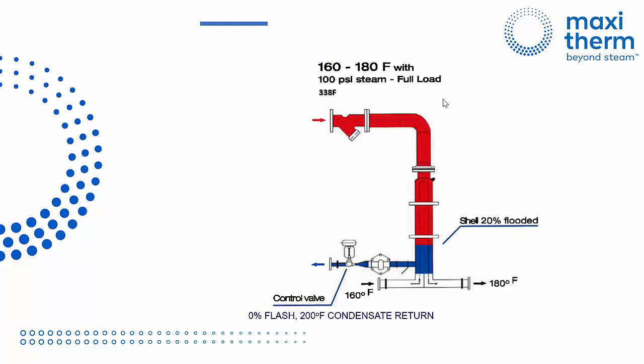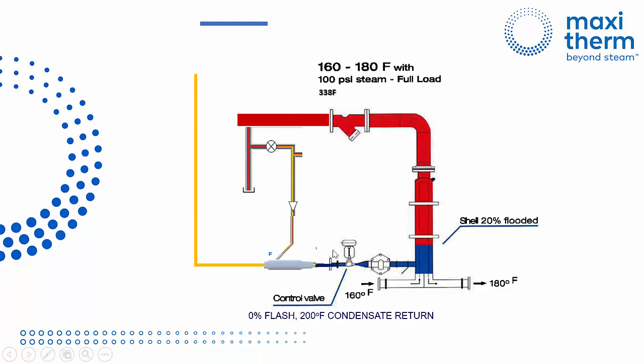Some of you might be wondering what you do with your steam trap drip legs. We provide a condensate mixer to mix the cold condensate coming out here with the drip legs, the steam trap drip legs on your system. Remember that with drip legs, there are only water drops coming in, so it's easy to handle. It's a sparger that we select based on the maximum loads and pressure. Since we're always pushing at 100 PSI, as long as the condensate back pressure is lower than your steam pressure, we never need a condensate pump.